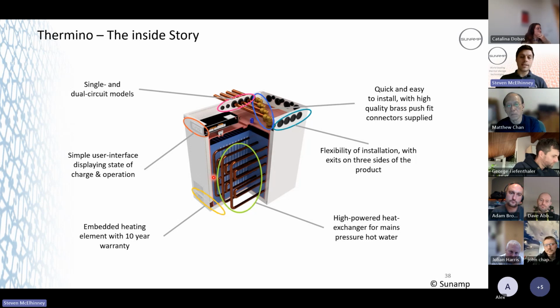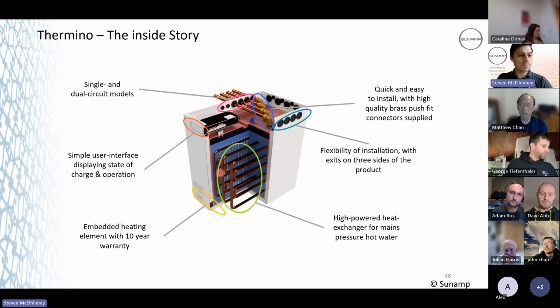So this is what I'm saying about capacity. If you've got customers that aren't using their heat battery properly, they might still think it's an immersion switch, for example. I'll put the immersion on for an hour, and then I get hot water. That's how we used to do it. I've done that for 50 years. That's not how it works. If you put that on for an hour, you're only half charged. That water's only being preheated until you get halfway, which means you will get hot water, but say for a 150, you might get a bath, but then you might not have enough to have a shower afterwards or wash your dishes.